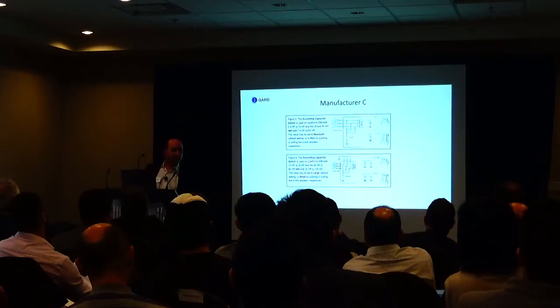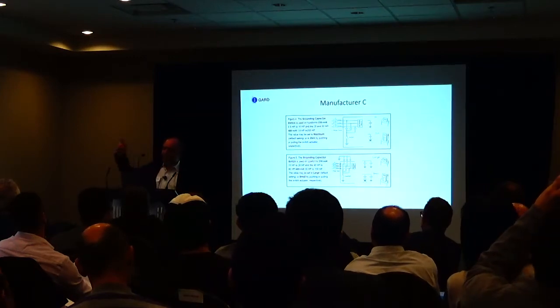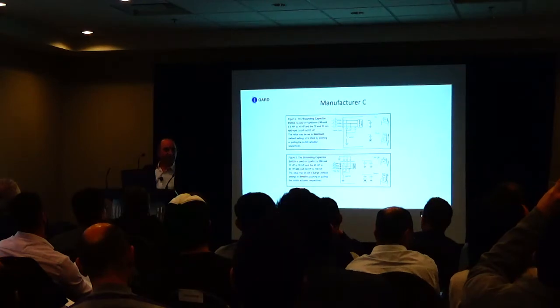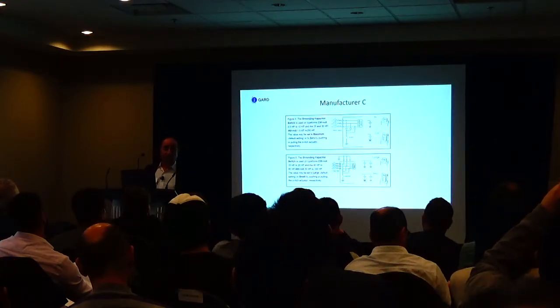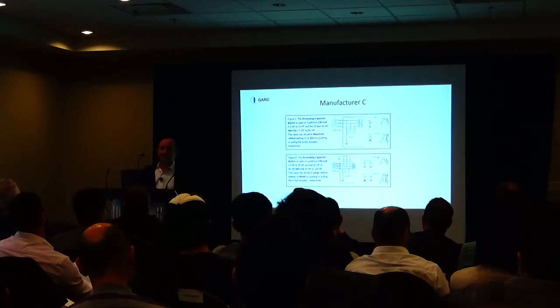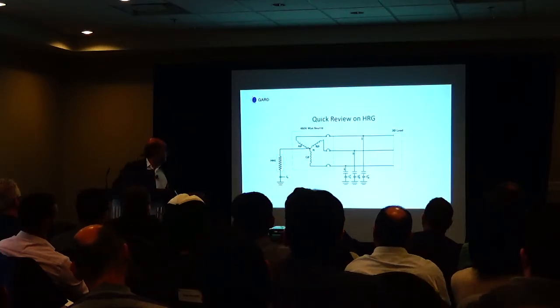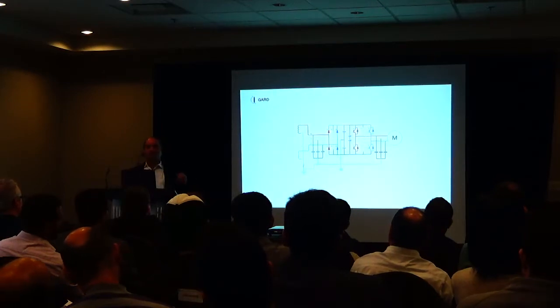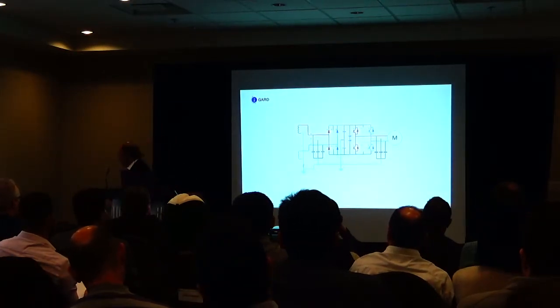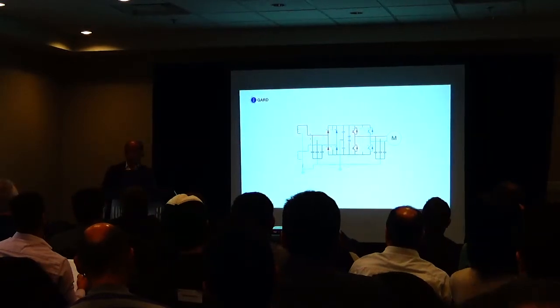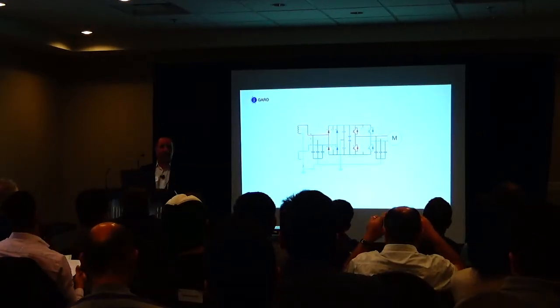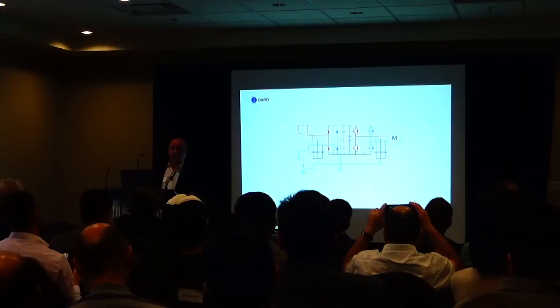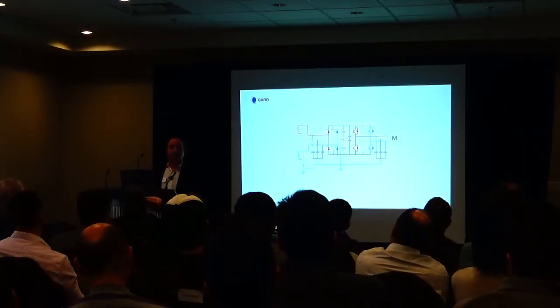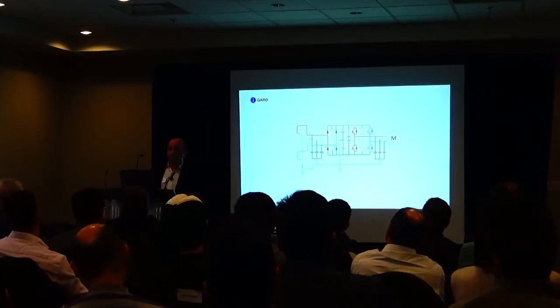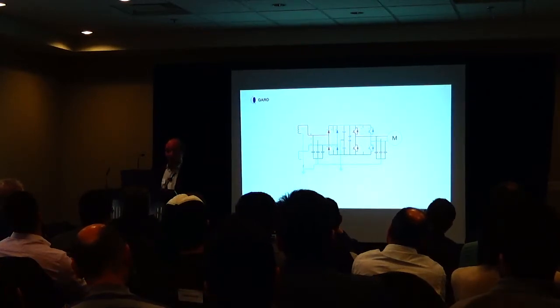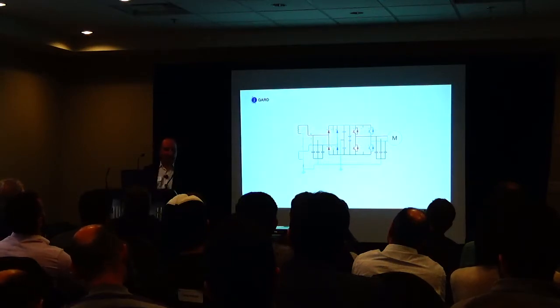So what happens when you have a capacitor on the front end of this thing and you have all this high frequency switching? What does the impedance of a capacitor look like when you have high frequency switching? Short circuit. All the frequency's gone. Variable frequency drives. Many people seem to think that variable frequency drives are separately derived sources, much like UPSs. A UPS is not a separately derived source. The only time you're going to have a separately derived source is if you go through a transformer. A variable frequency drive is not a separately derived source.